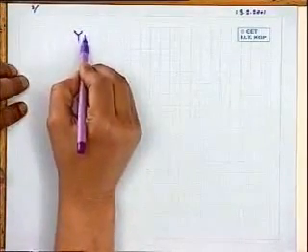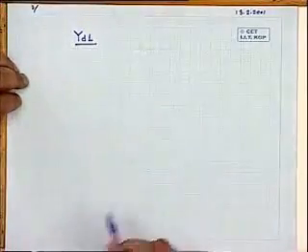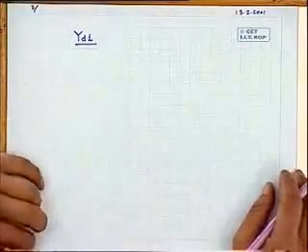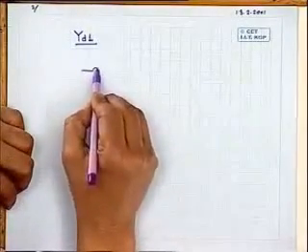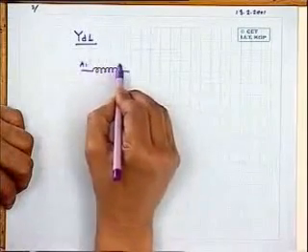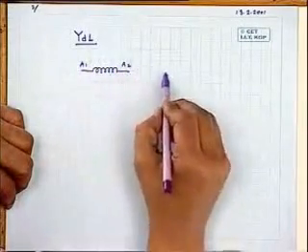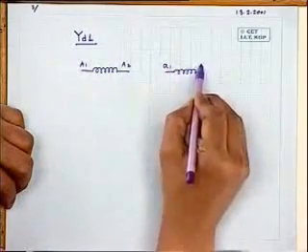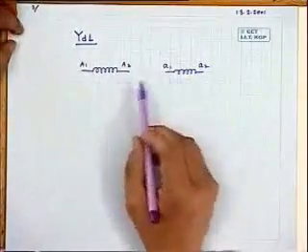For example, I want to do the YD1 connection. Just very carefully you see how I am doing. Suppose I want to realize the YD1 connection of a three-phase transformer whose primary and secondary windings have been identified with proper terminal markings as A1, A2 and on the secondary small a1, a2, and as I told you, these 1, 1 are dots.